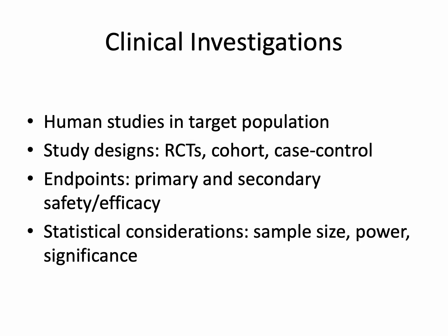Clinical investigations evaluate device safety and effectiveness in humans. Study designs may include randomized controlled trials, cohort studies, or case control studies. Primary and secondary endpoints capture efficacy and safety outcomes, and statistical planning ensures appropriate sample size, study power, and significance testing. Robust clinical evidence is required for higher-risk devices and is a central component of FDA PMA, Health Canada Class 3/4, and EU Class IIB/3 submissions.